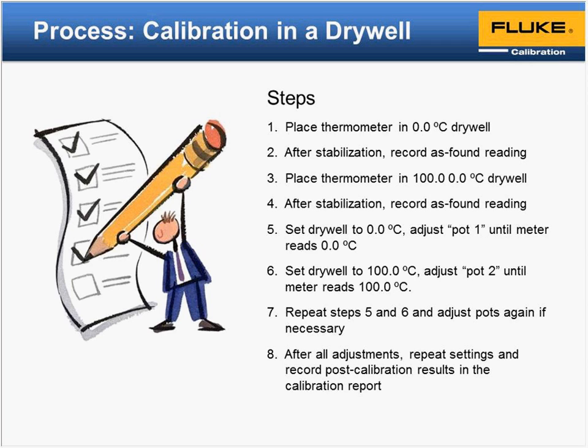In our example, we were trying to stick within that plus or minus 0.2. We're down at 0 and we're getting a 0.1, but then at the top end we're only seeing a 99.9. We're still within that window that we want to be in, but you can see how the top may affect the bottom. So again, things to keep in mind as you're doing these calibrations.